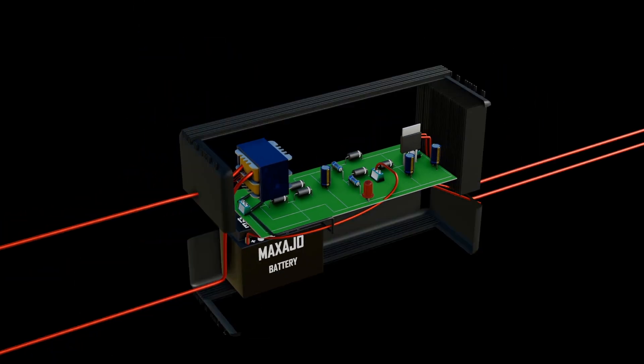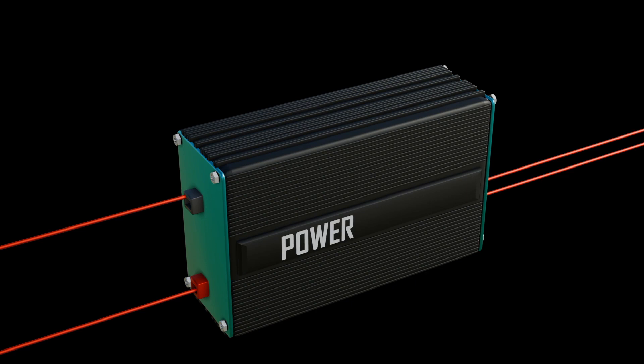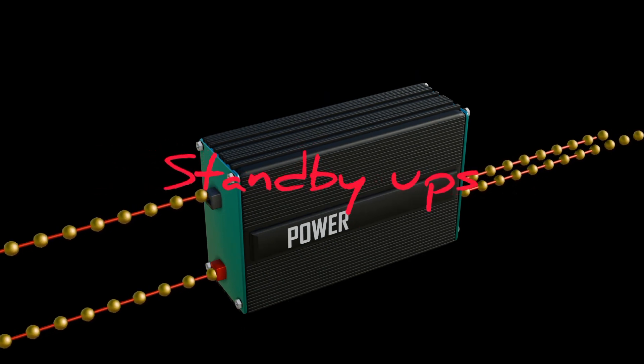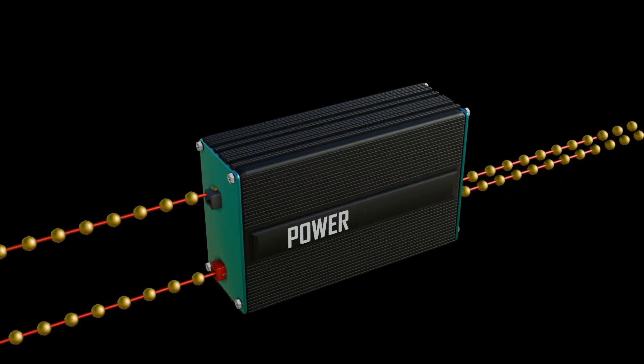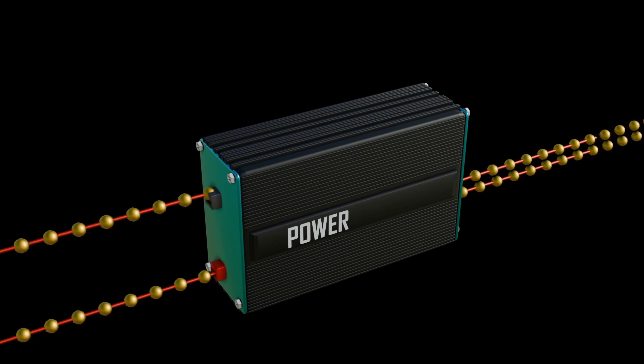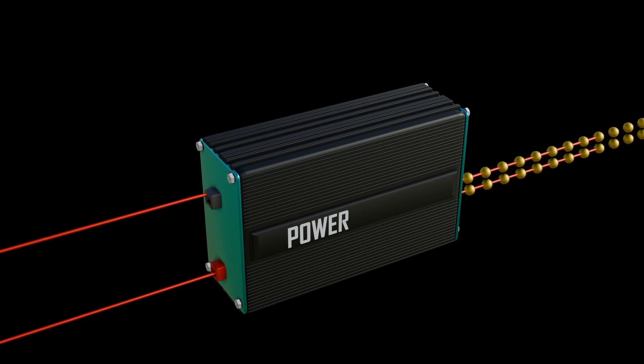Something to note is that this type of UPS is called standby UPS. The standby UPS runs the computer off of normal utility power until it detects a problem. At that point, it switches very quickly, about 5 milliseconds or less.